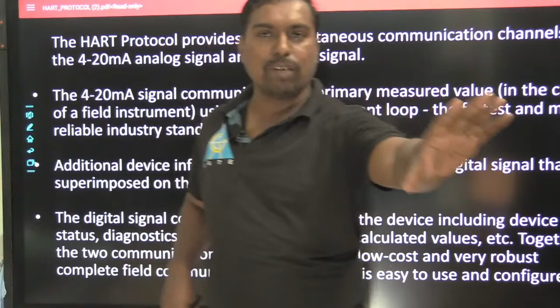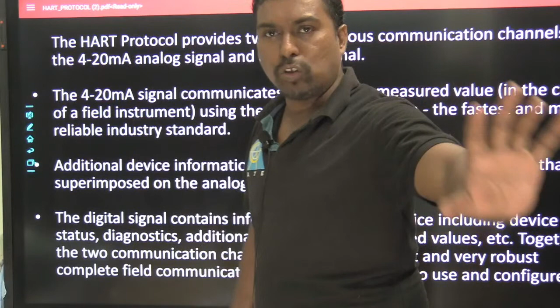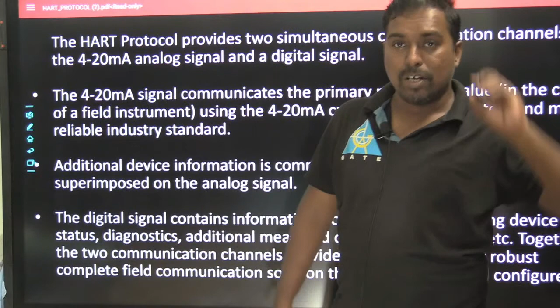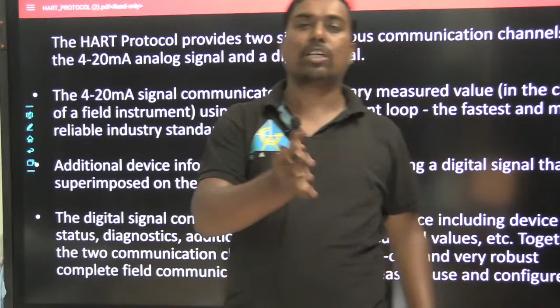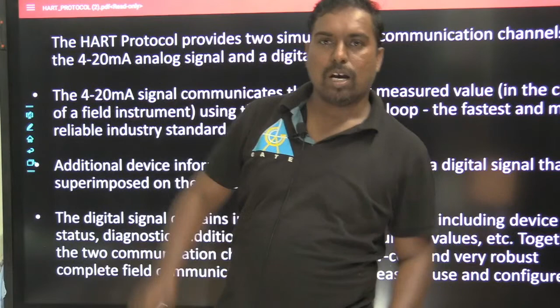That means I have a sensor, I have a field device. Let us take a thermocouple. It is 4 to 20 milliamperes. By using the 4 to 20 milliamp concept, it has converted the temperature into a signal. Now, there is another one, a pressure transducer. By using 4 to 20 milliamperes, it converted 3 to 15 psi to 4 to 20 milliamperes. Do you understand? Are you getting my point, boards?